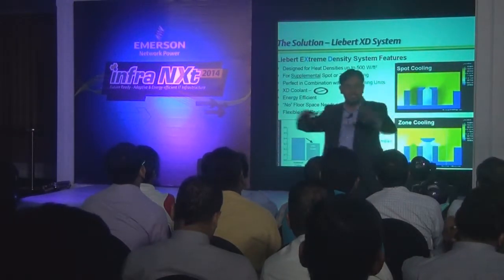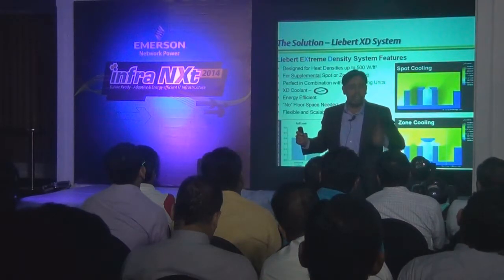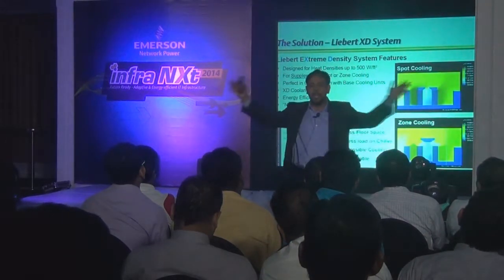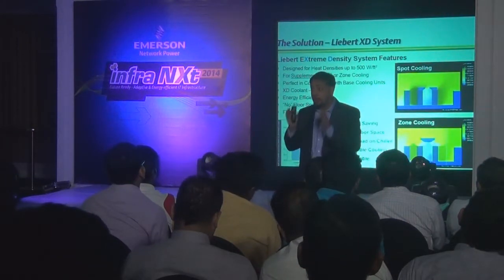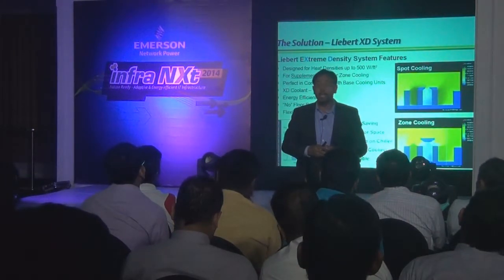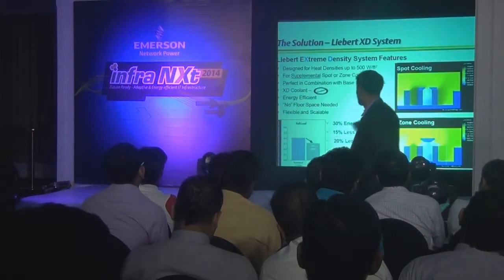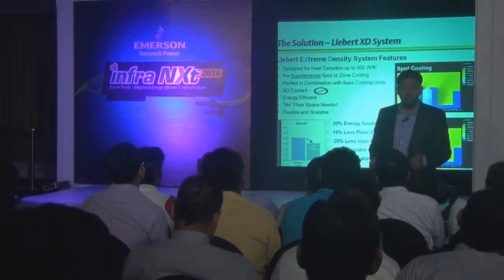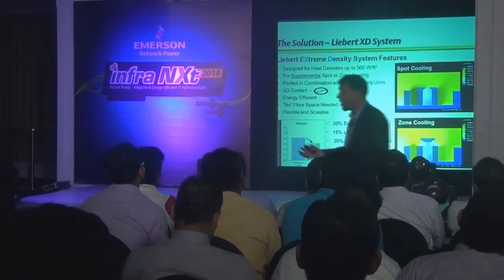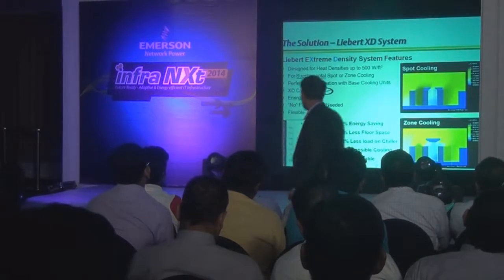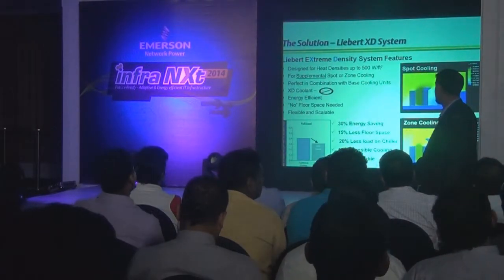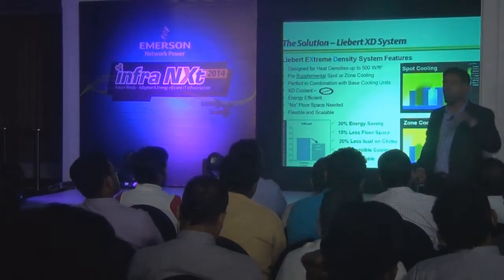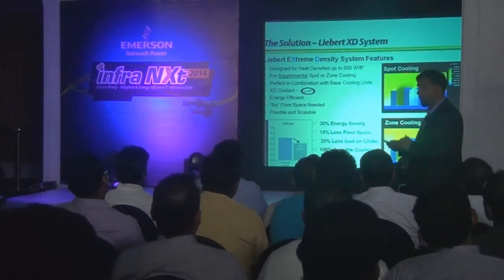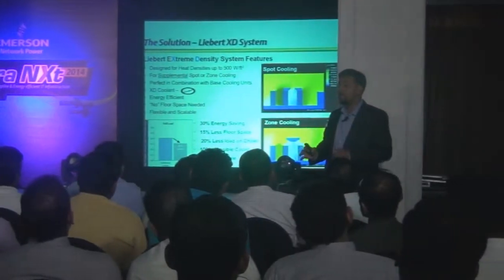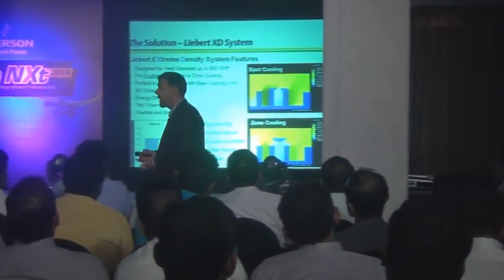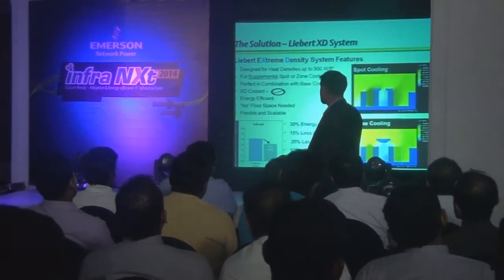Assume you have this size of a room, each rack having 40 kilowatt load, you can have so many racks and so much power utilized, given the minimum footprint of the data center. And you achieve the highest efficiency. There are cooling modules which utilize minimum fan power, and there are also cooling modules which do not have any fan power, like a rear door heat exchanger. So what you get here is there is no water coming to the data center. We bring only refrigerant to the data center, and you achieve the highest efficiency, and there is no floor space required because it is either sitting on the rack, on the ceiling, or behind the rack itself at the rear door. So your space is saved.